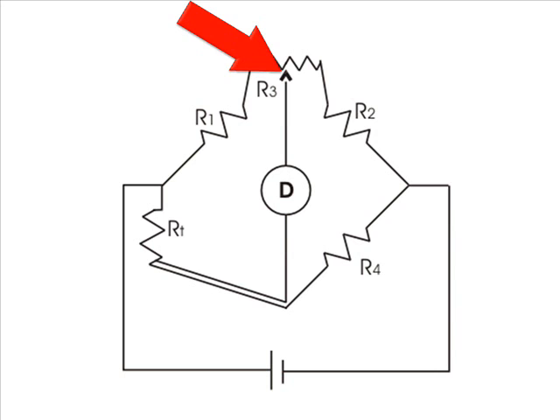Here the balance is also achieved by adjusting the sliding contact on the variable resistor. In this situation, the contact resistance of the sliding contact does not come under bridge circuit, rather it comes under galvanometer circuit. Hence this contact resistance does not affect the balance of the bridge, hence temperature reading would be more accurate.